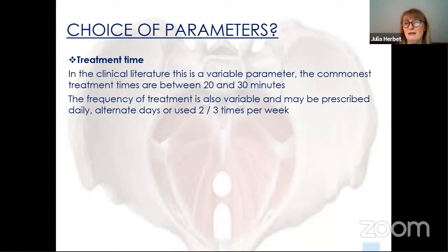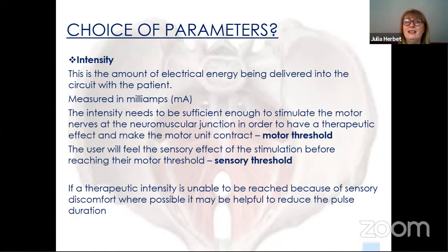And actually, if they can do some pelvic floor contractions, stimulation might be an adjunct to them doing their exercises as well. Now, the key parameter that's really important is that this patient turns up the intensity sufficiently high to get that motor contraction to happen. And the problem we have in any stimulation, and particularly in the pelvic floor, is that the sensory nerves will sense the stimulation way ahead of the motor nerves. So with a few milliamps, you can be feeling stimulation on your sensory nerves, but you're actually not getting any muscle contraction. So it's important that they're trained to get through the sensory threshold and keep turning up until they feel the contraction. They should feel the electrode being drawn up and in if it's actually working.